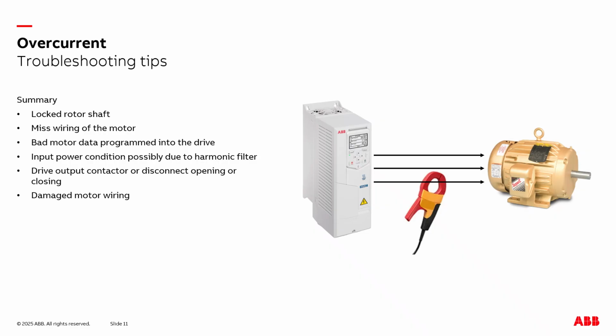Verify you have good input power. The most common issue when I talk about input power is passive harmonic filters, or trap filters as they're also known. This can cause issues on the output of the drive, even though the filter is installed on the input of the drive. And last, verify that you don't have any output contactor or disconnect opening between the drive and the motor while the drive is running.